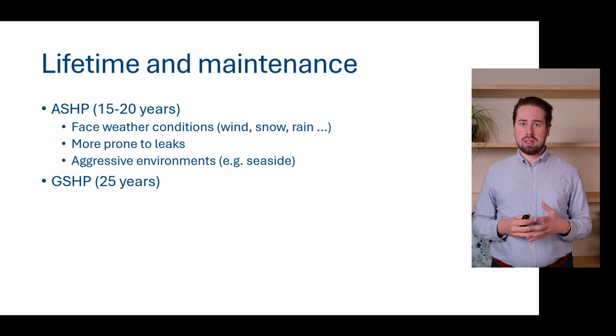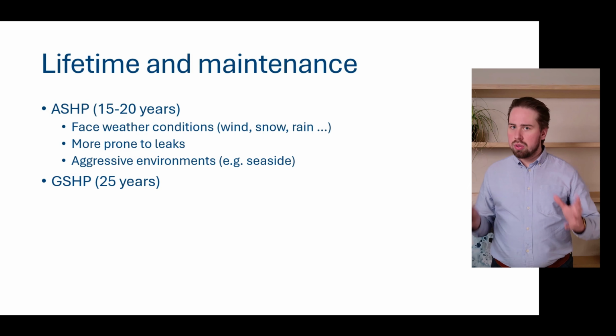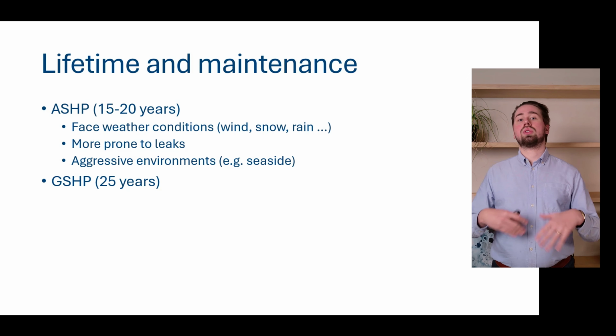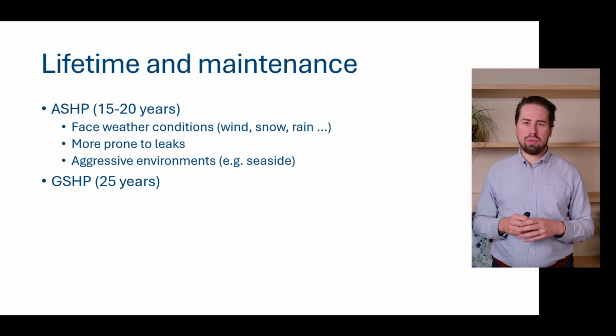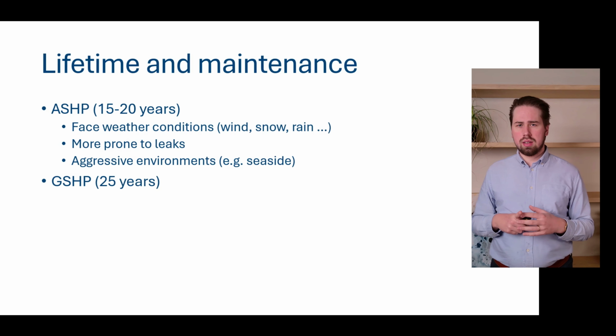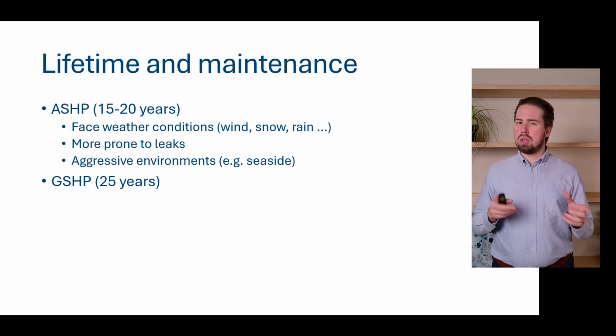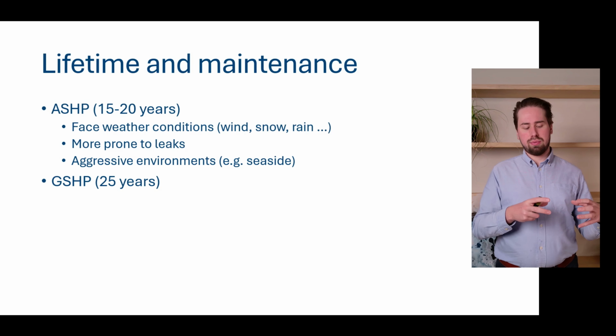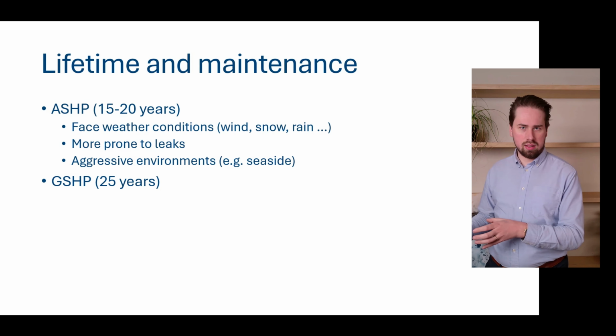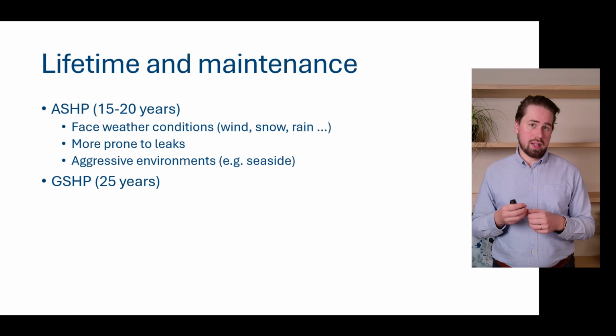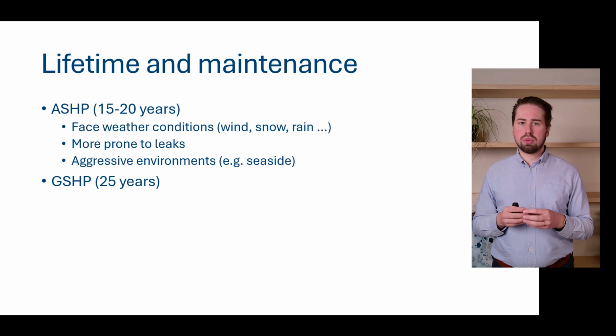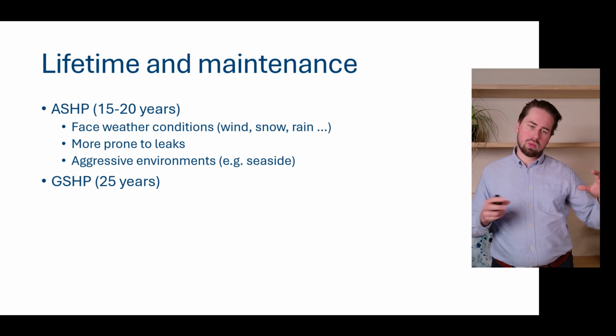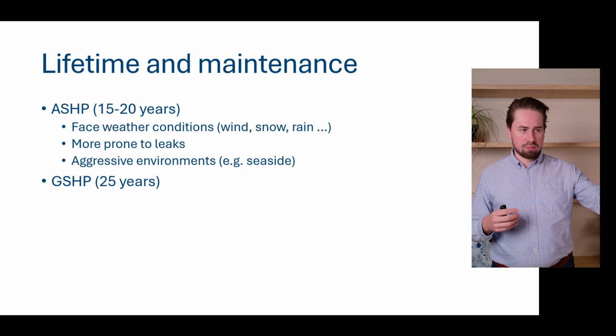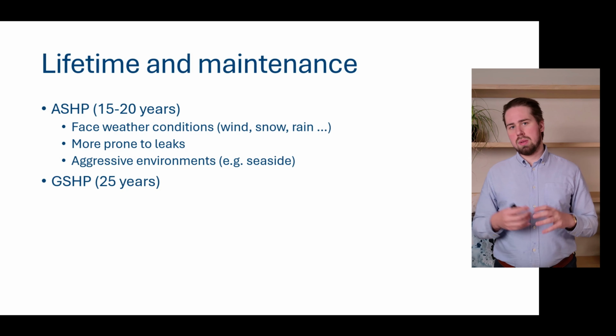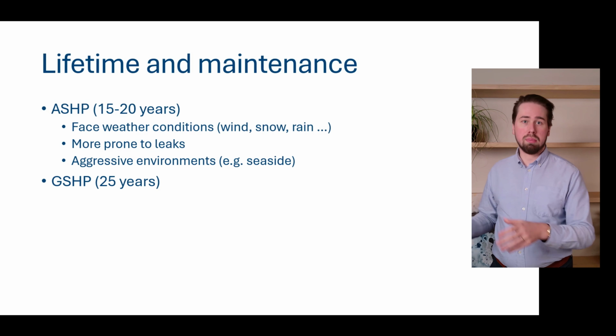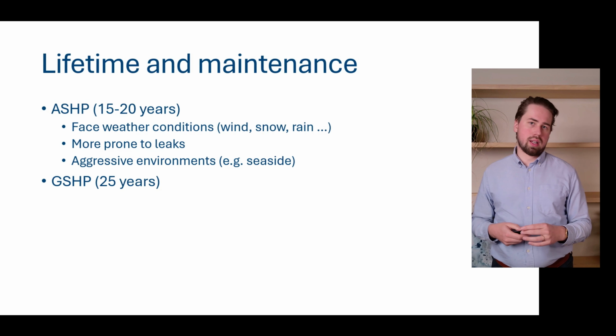Now, a ground source heat pump is installed safely in-house, not facing the weather conditions, so it also has a better lifetime, typically around 25 years. Now, I also want to say that with the movement towards propane machines, some manufacturers, like for example Weishaupt, have opted for creating ground source heat pumps that are placed outside. Because propane is a flammable and explosive gas, there have to be solutions for that, so some manufacturers choose to vent their heat pumps, to place them under pressure, so in case of a leak, the propane is evacuated out of the building. Weishaupt has opted for the solution of just placing the whole heat pump outside of the building, so there is no problem with leaks or explosive conditions there.